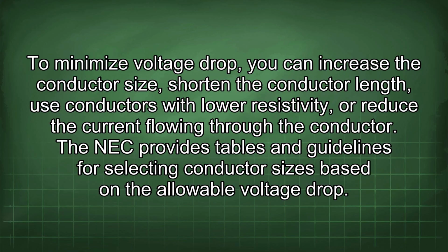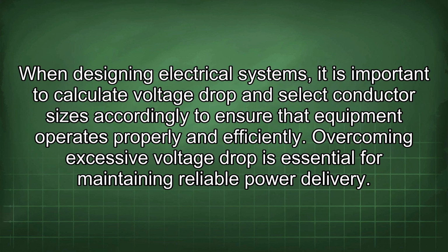The NEC provides tables and guidelines for selecting conductor sizes based on the allowable voltage drop. When designing electrical systems, it is important to calculate voltage drop and select conductor sizes accordingly to ensure that equipment operates properly and efficiently. Overcoming excessive voltage drop is essential for maintaining reliable power delivery.